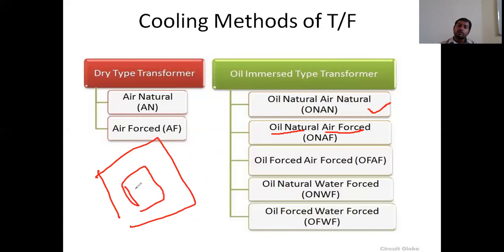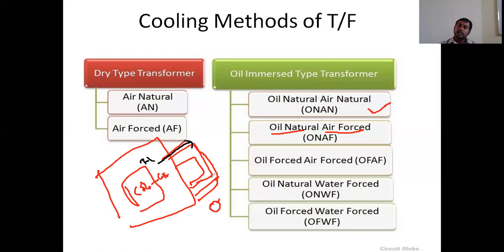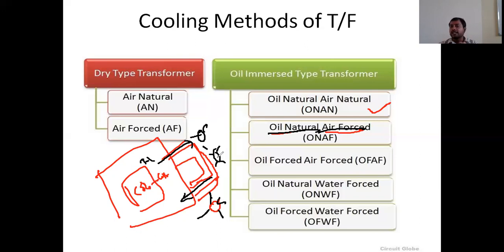In the ONAF system, the transformer tank has the core and winding inside, with outside radiator pipes. Oil naturally flows — high temperature oil flows into the radiators and low temperature oil flows into the transformer naturally. That is why this is called oil natural. Air forced means we need to use separate fans outside the transformer tank connected to the radiators. When the fans are turned on, air is forcibly circulated into the radiators and outside pipes of the radiators, so that the oil temperature reduces very quickly using forced air.